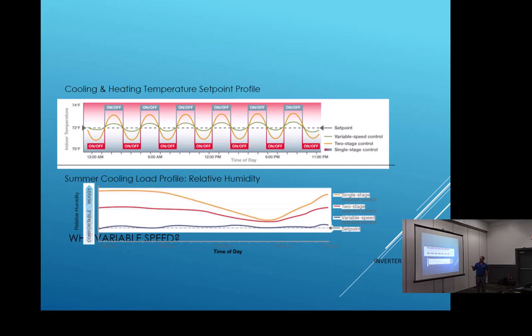Very energy efficient. The two-stage control gives us a little bit more of a swing here, right? So we could have a little bit, not quite as much comfort and energy savings, because now we're going from 1 degree, maybe up to 2 or 3 degrees swing, right? So we're still more energy efficient than that fixed speed compressor down here, okay? But we're not controlling the comfort as much or the energy efficiency. Still more energy efficient than the fixed speed, but not quite as good as the variable speed, okay? So if someone wants, you usually get them good, better, and best. Your two-stage maybe is probably your better, and your fully variable is your best, okay?